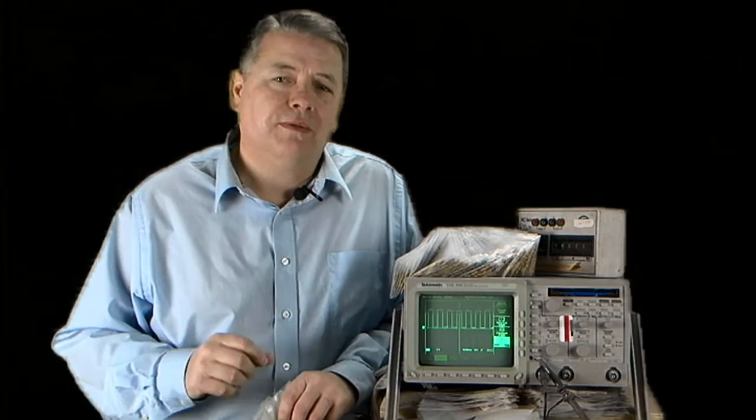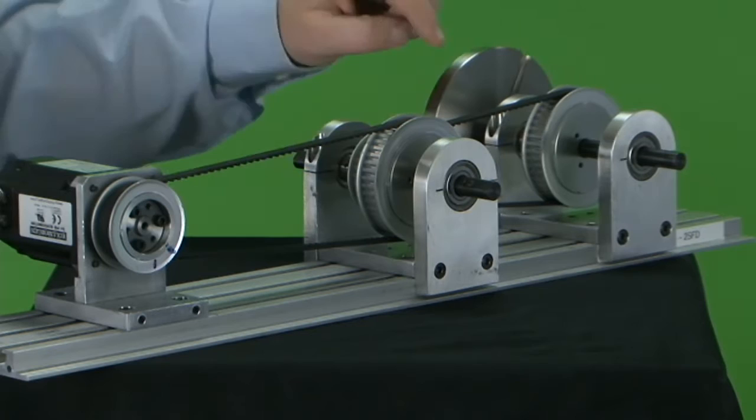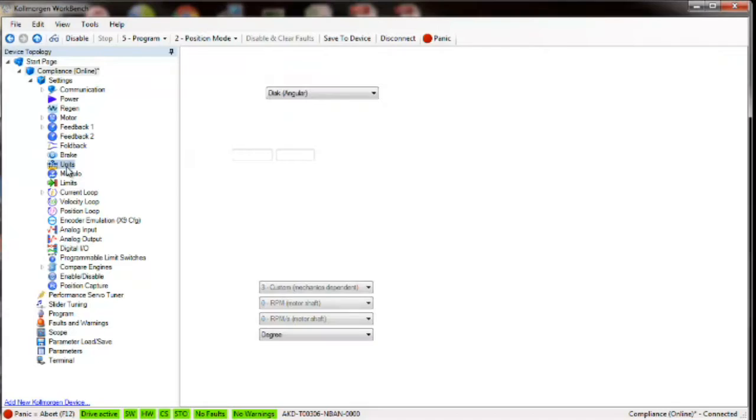The system to be tuned is a very compliant two-stage belt system with an inertia ratio of 50 to 1. The belts have been tightened to the manufacturer's specifications. The units have been set up for a disc using the mechanical position of the load rather than the position of the motor and a 2.7 to 1 gear ratio.